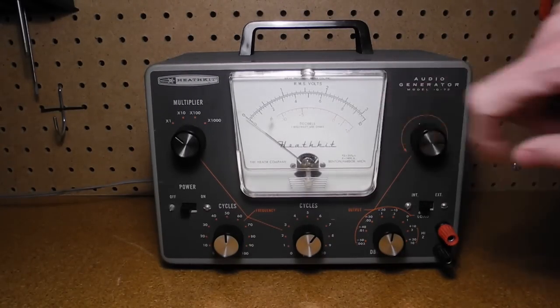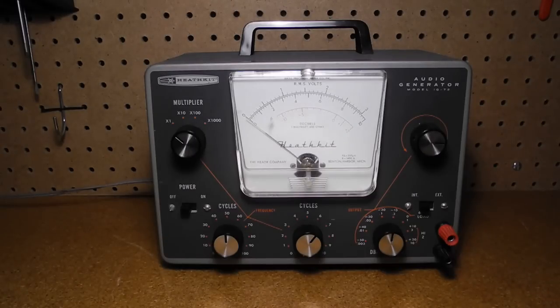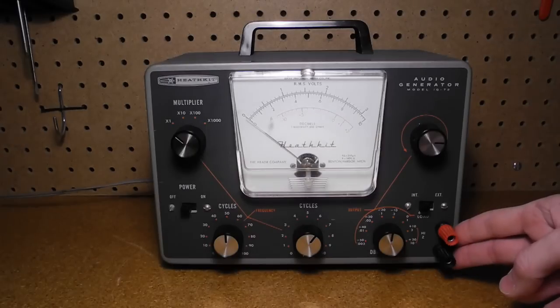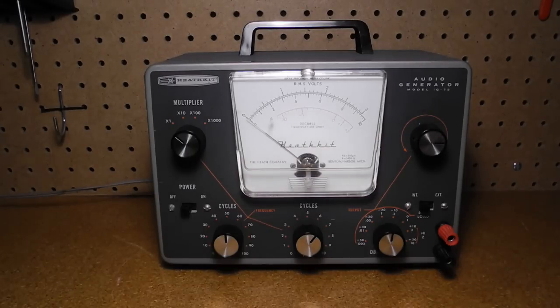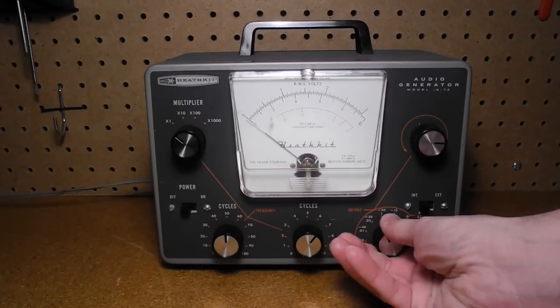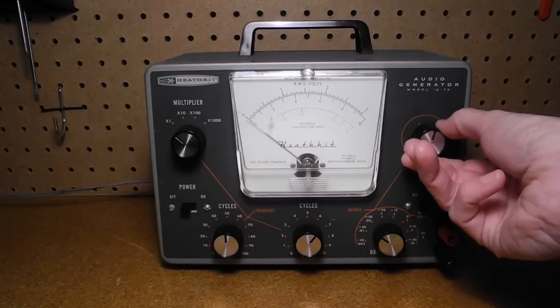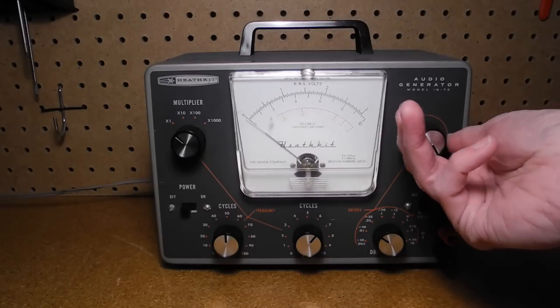A meter which indicates the level of sine wave output in volts, RMS, and decibels or dBm. A dBm is a power level of 1 milliwatt, usually standardized against a load of 600 ohms. The level has to be scaled by the output level range, so for example it indicates 0 to 10 volts on the 10 volt range and 0 to 1 volt on the 1 volt range. The two sine wave output terminals. The sine wave output level controls. The coarse adjust selects one of 8 ranges and the fine adjust controls it continuously from 0 to maximum.